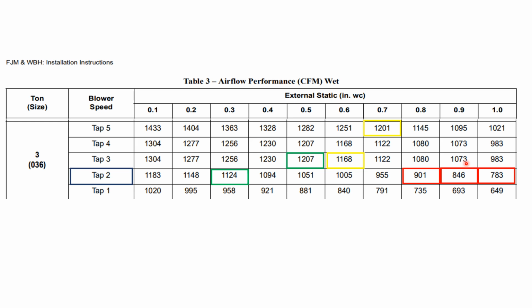Now, if you look back at the map, that's 2 bedrooms we're losing, or a living room size area we're losing. So we have to get our 1100. Here we look at these 2 areas in the yellow, which mean these are over 1115. So if my static pressure was 0.6, I could move my tap up to 3, and as long as I'm in that 0.6 static range at speed tap number 3, then I'm going to get 1168 CFMs.